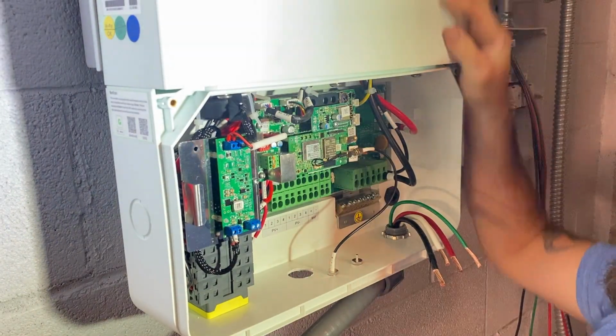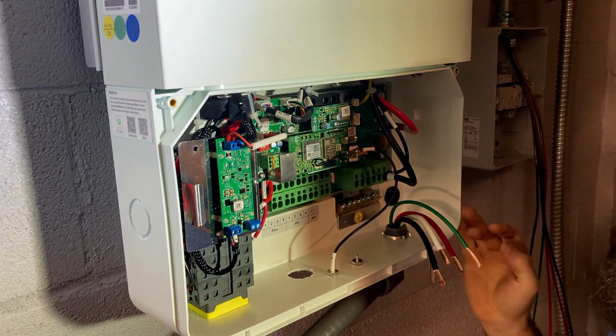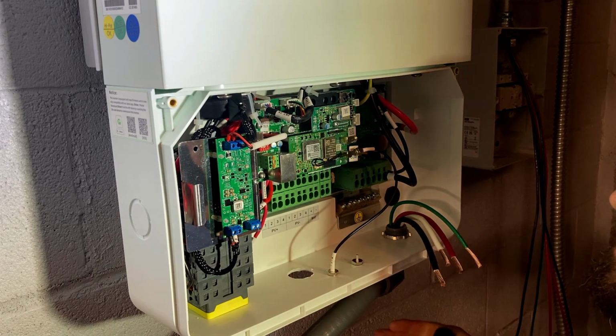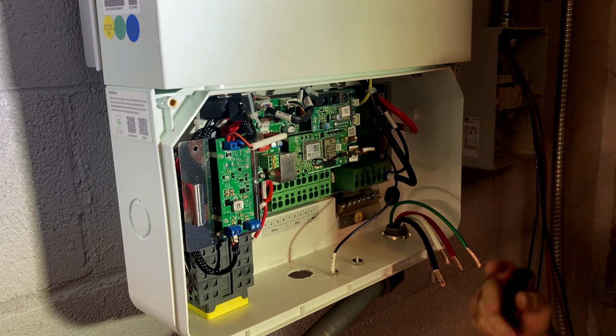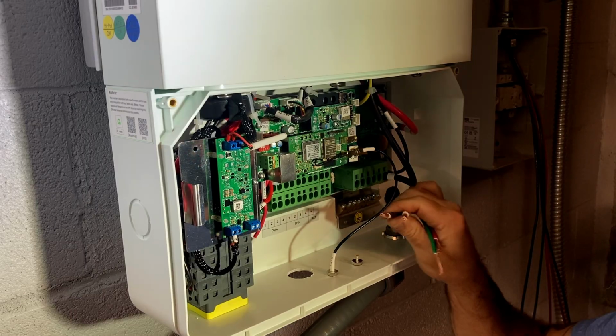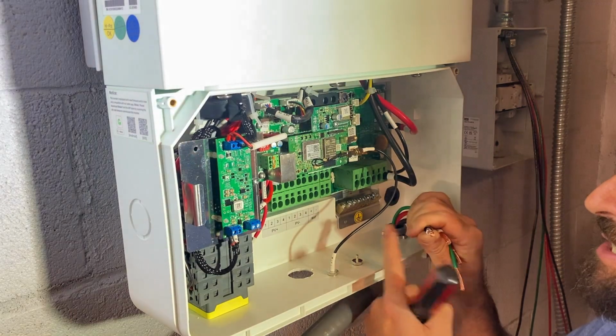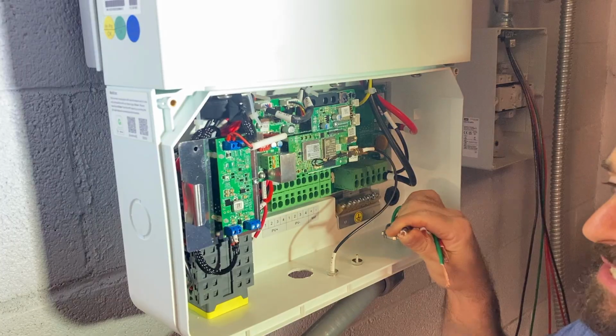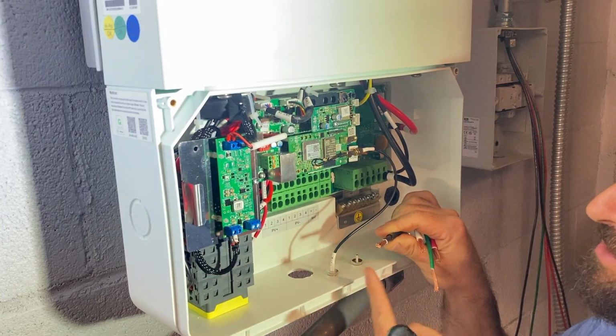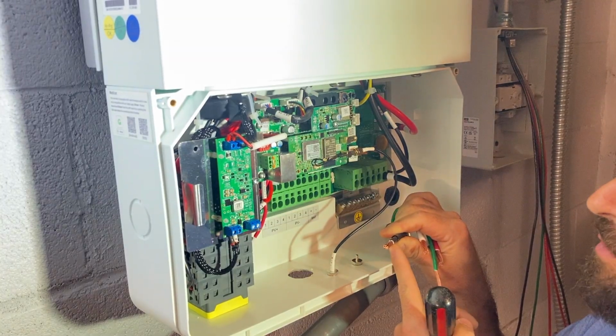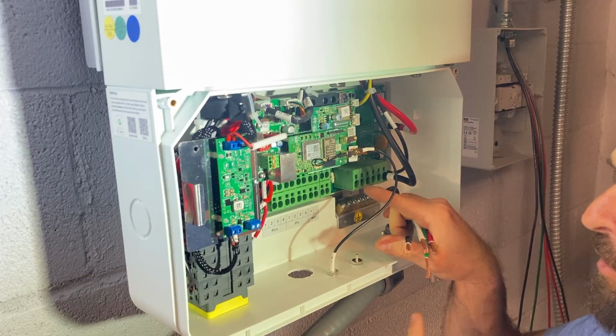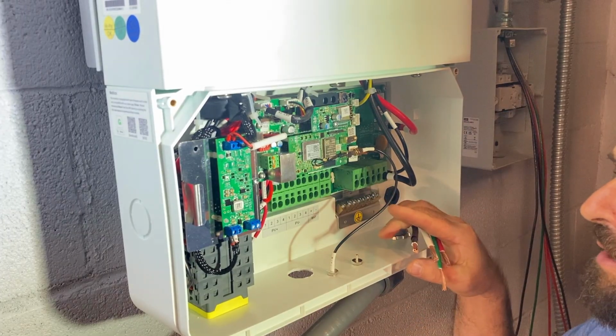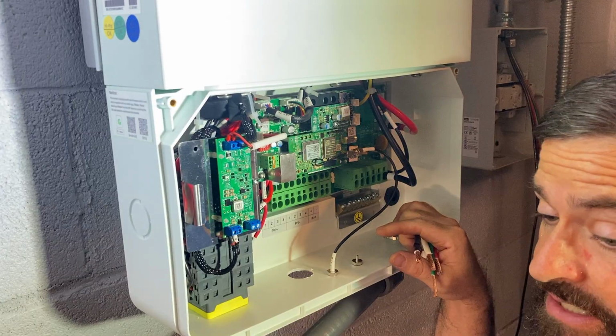So the Growatt manual is suggesting you use wire ferrules for a lot of these terminations, but my opinion is it's just not necessary. I've been doing this forever. If you can't actually get all the strands in the terminal, then yes, you should use wire ferrules. But as long as you know what you're doing and make sure all the strands land firmly in the terminal block, my opinion is they're just not necessary.